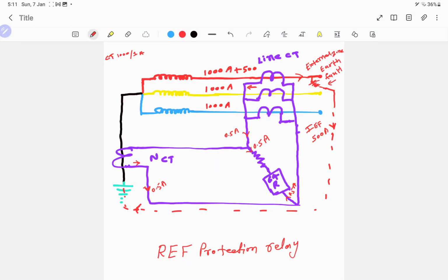Hello, today we will talk about the REF protection relay, restricted earth fault protection relay. We will learn the basic principle of the REF relay. So here is the LV winding of the transformer, or could be HV winding of the transformer. Basically, it's used with the star connected winding, and REF protection relay is used to protect the internal zone of the star winding. So from the neutral to the winding, internal winding of the transformer.